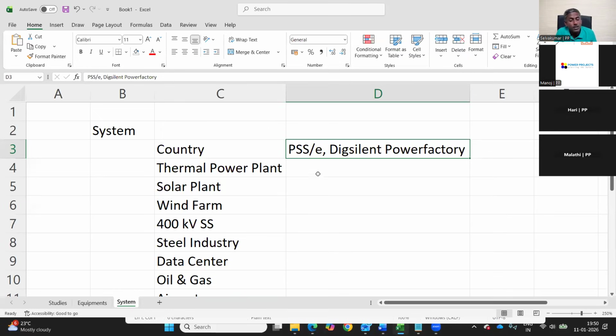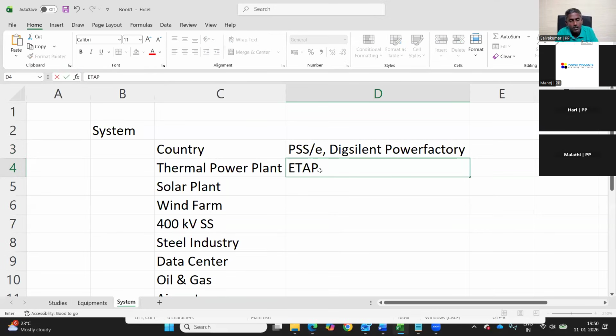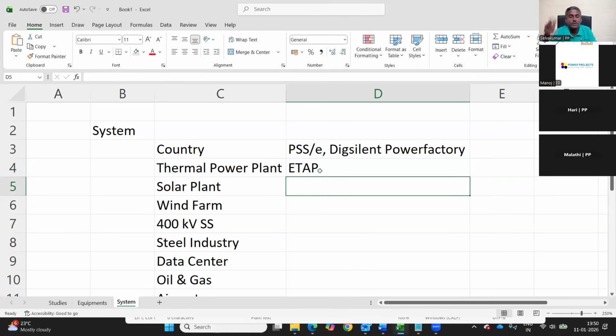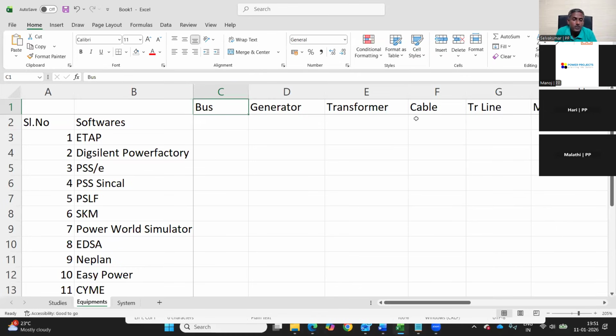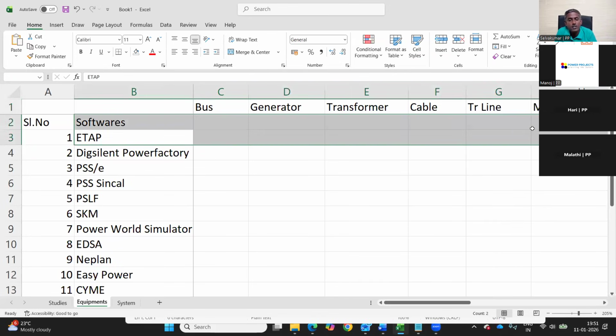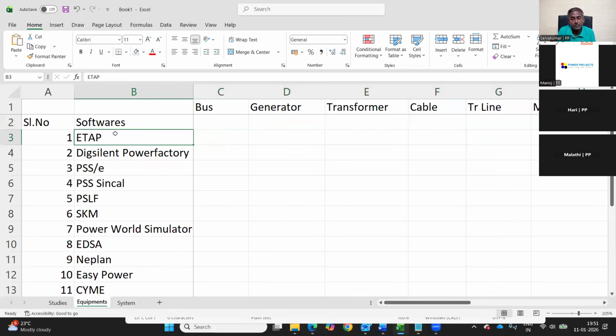But if you're talking about a thermal power plant and its auxiliary power systems, the preferred software is ETAP, SKM or CYME, etc. So if you have a grid step-down transformer and then cables, motors, bus ducts, CTs, relays, circuit breakers, isolators - from the equipment perspective, ETAP is green for all these equipments. That makes the software ETAP more suitable, not for complete country level power systems.